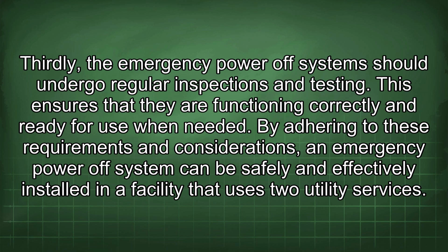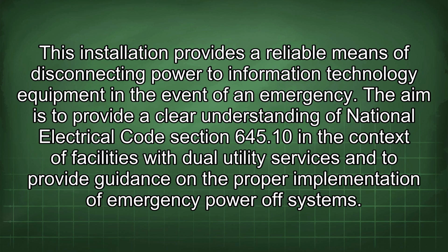By adhering to these requirements and considerations, an emergency power-off system can be safely and effectively installed in a facility that uses two utility services. This installation provides a reliable means of disconnecting power to information technology equipment in the event of an emergency. The aim is to provide a clear understanding of National Electrical Code Section 645.10 in the context of facilities with dual utility services and to provide guidance on the proper implementation of emergency power-off systems.